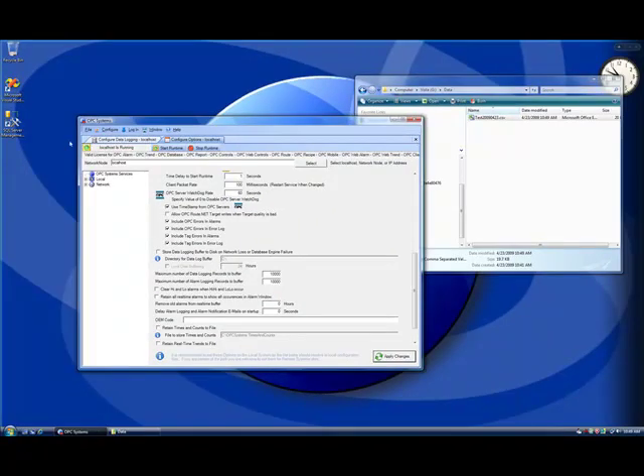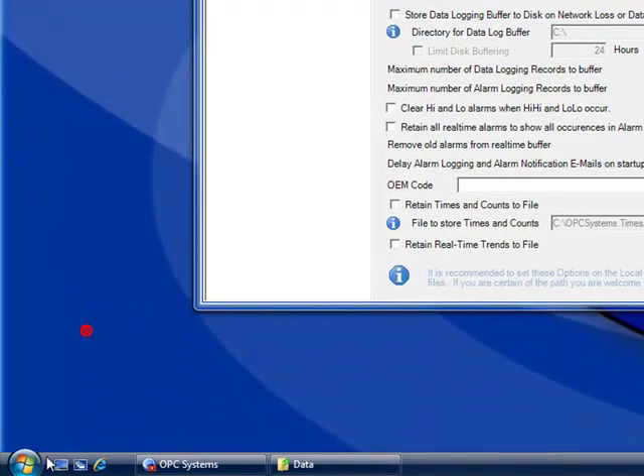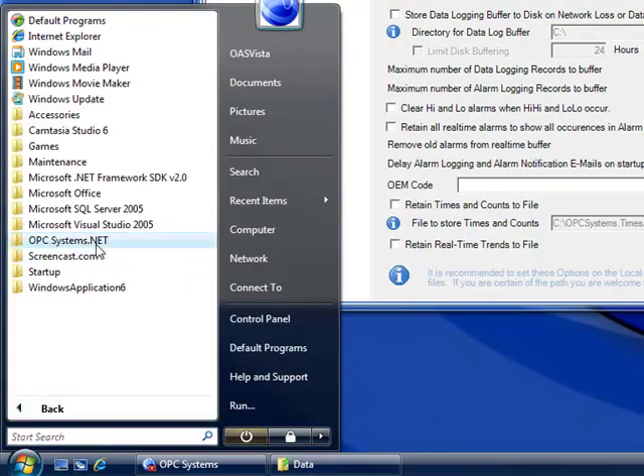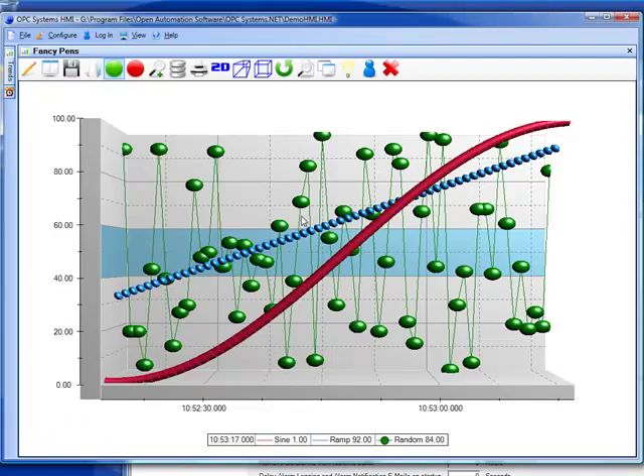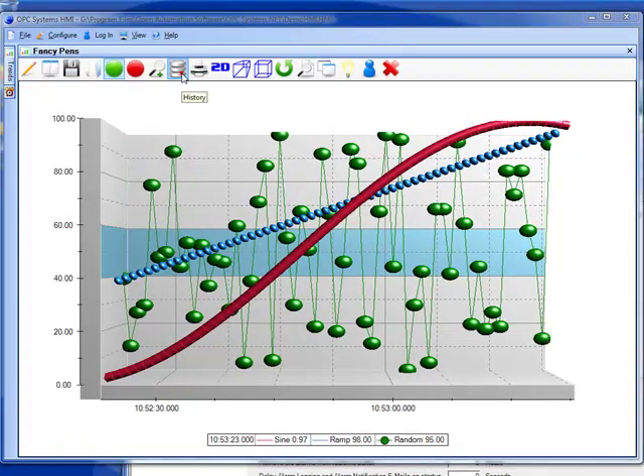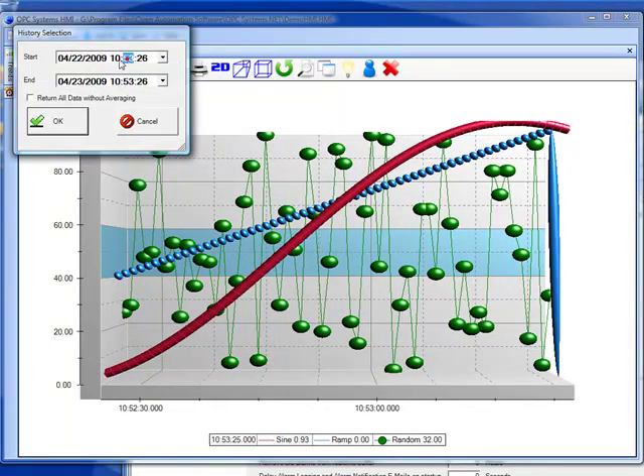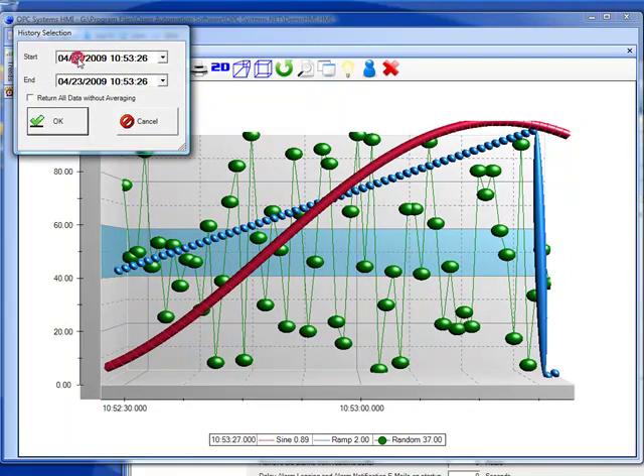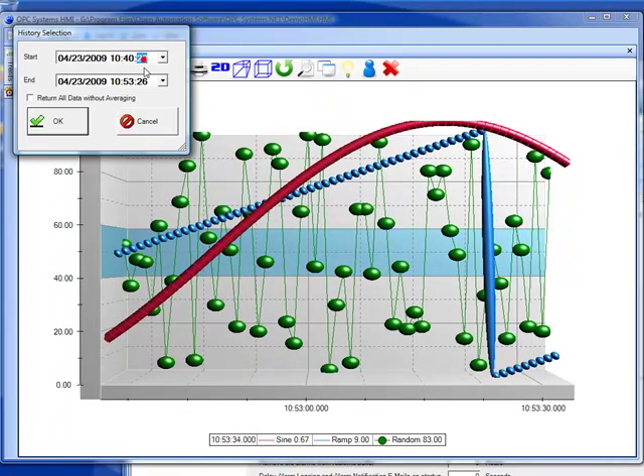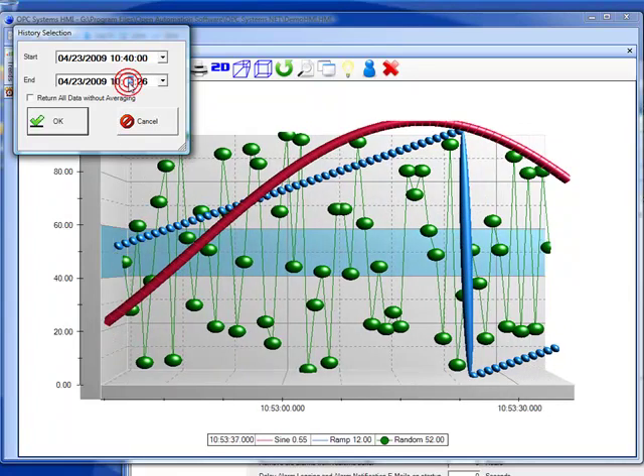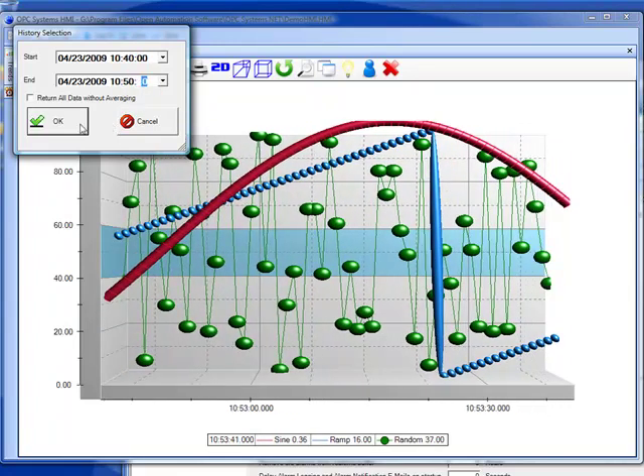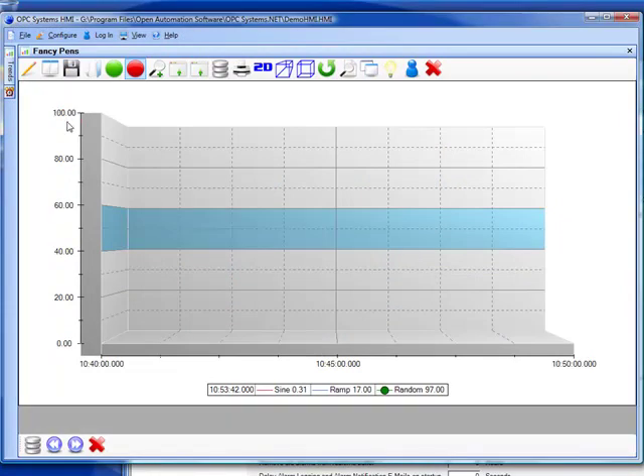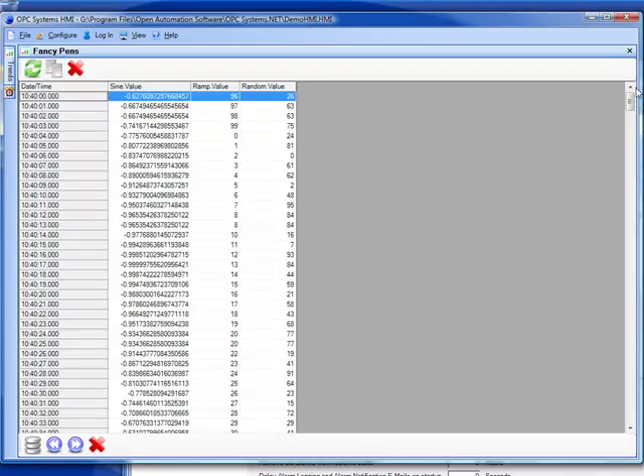Let's see how we would use the opctrend.net product to replay data from the database. Remember that the data logged is in an open format, so you can use any third-party software that can make a database query. Let's use the OPC systems HMI container that was demonstrated in the training video of opctrend.net. Here we see the real-time data from the local OPC system service. To make a history call from a trend window, select the history button on the toolbar. Specify your start and end time frame. Remember that the opcdatabase.net table format is open, so you can use really any third-party database product that can make a generic query. We select OK. The OPC system service will then go to the database, query the data from the data, and return it back to the trend for us. We can then analyze the data using the data grid and see the raw values from the database.